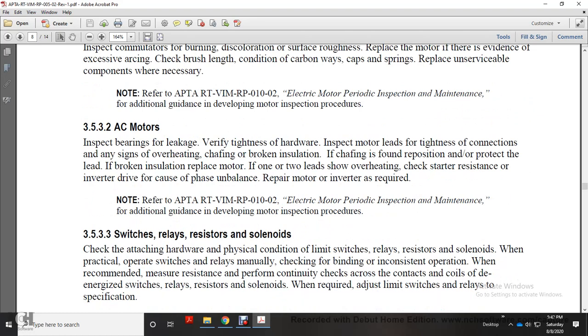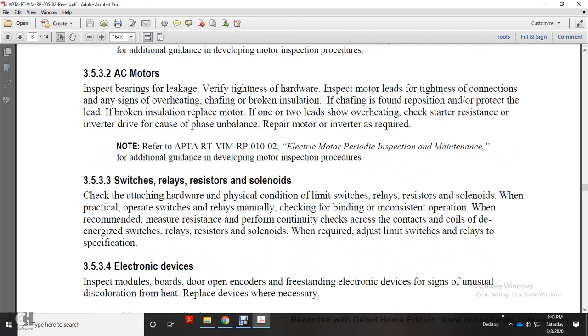Alright, 35232, AC motors. Inspect bearings for leakage. Verify the tightening of the hardware, inspect the motor leads, tightening for the correction, and connection for any signs of overheating, broken insulation, and reposition or protect the leads. If the insulation is broken, replace it. If one or two of the leads show overheating, check the resistance of the inverter drive, the cause of the phase unbalance, repair, and replace the inverter as required. Refer to the APTA RT VIM recommended practice 01002 for electrical motor periodic inspection maintenance for additional guidance developing inspection procedures.